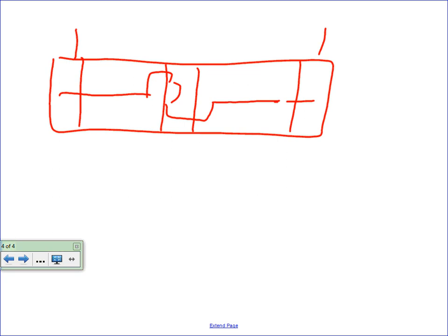So obviously if you use Kirk keys or key interlocks, it's a manual system. If you lose the power to this source, you open the main up. Once you do that, it allows you to pull the key out, put it into the tie, and that allows you to close the tie, so now you're feeding the power for both sides from that main, or vice versa. And then when you have both sources, you open the tie, you close the main, and now they act as separate entities.